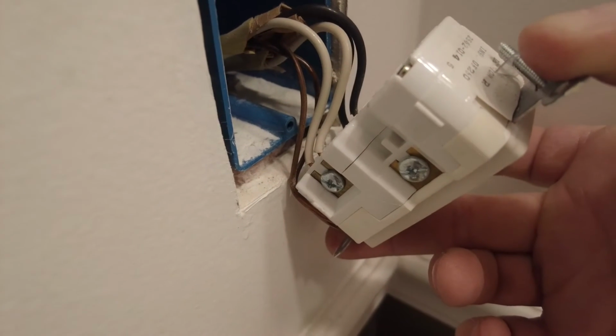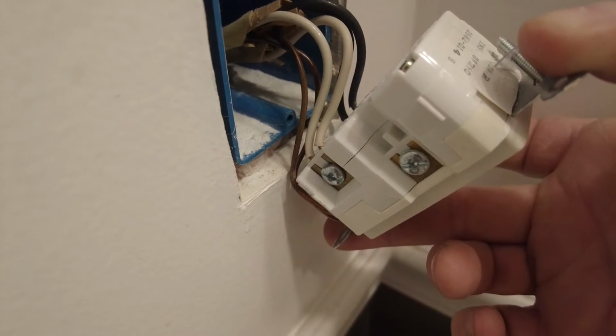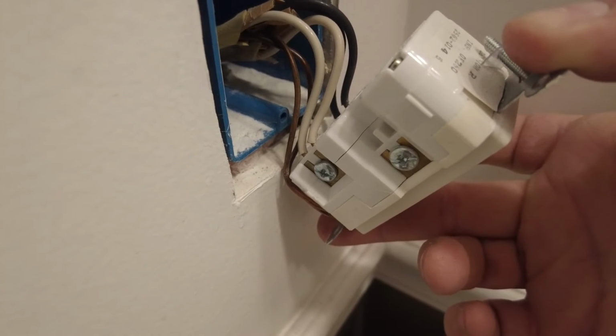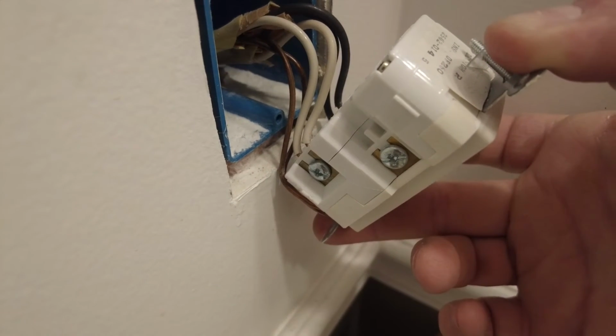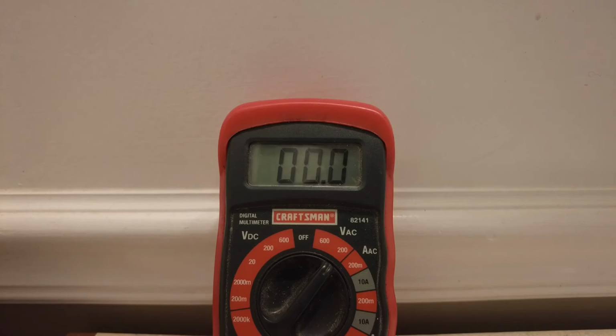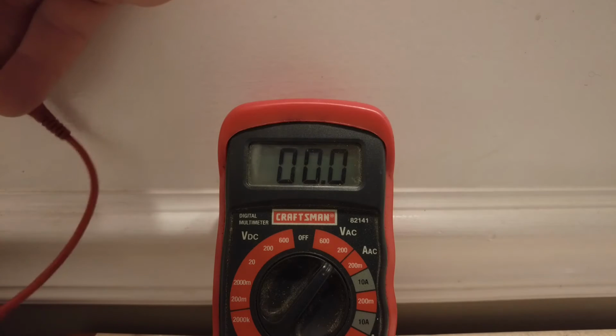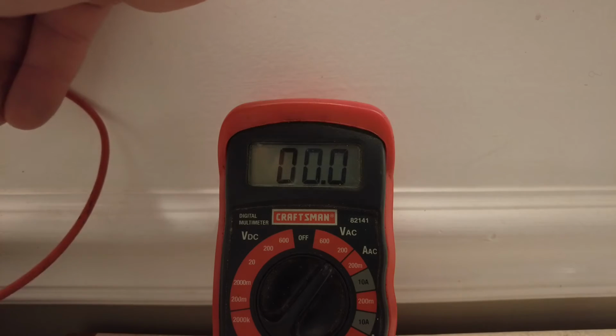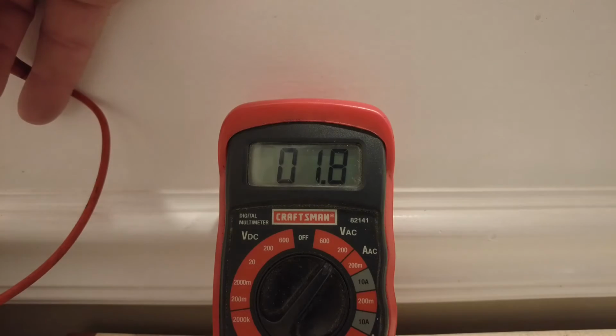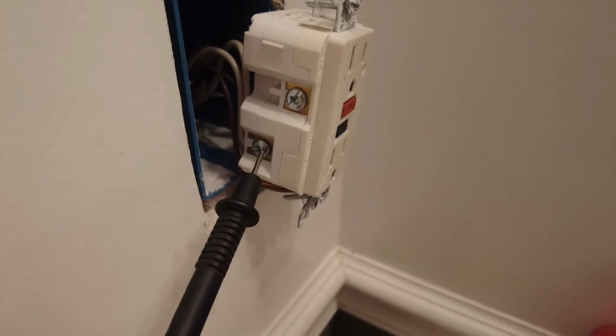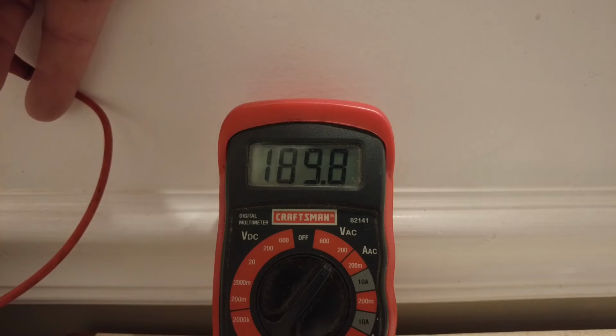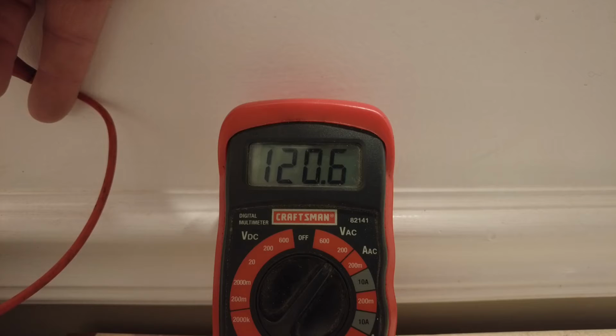You can see the wires are pushed in from the back, with white on one side and black on the other. That means I should be able to check if there's power coming to the outlet by putting one lead on one side and one lead on the other, on the screws, and paying attention to the voltmeter. That confirms we've got power coming to the outlet.